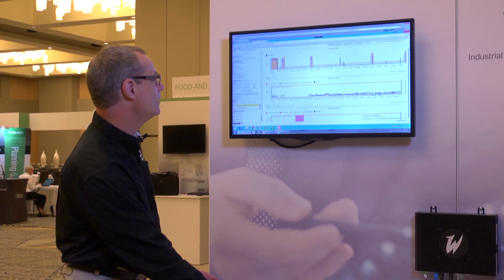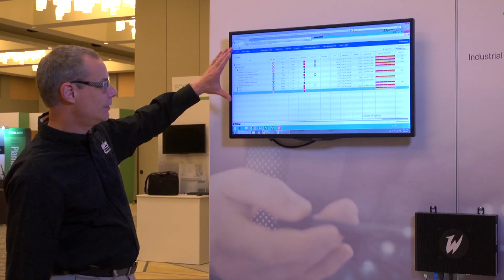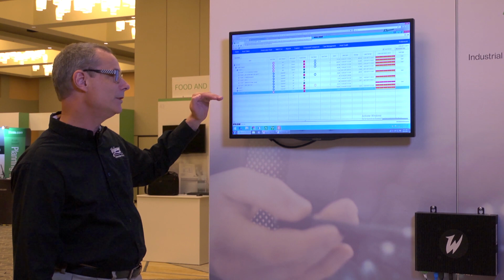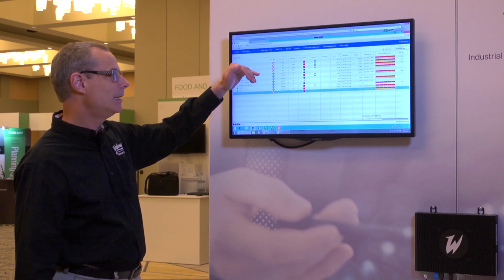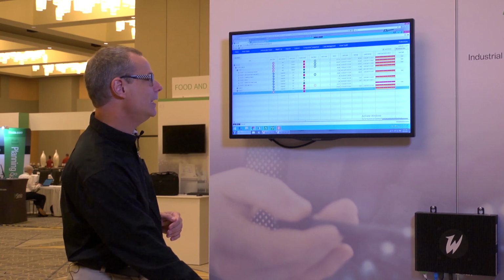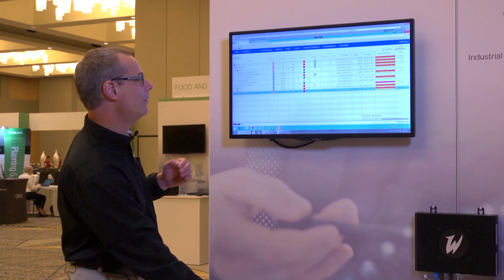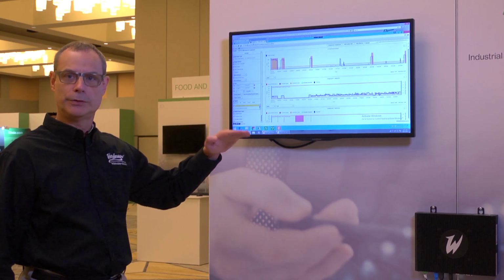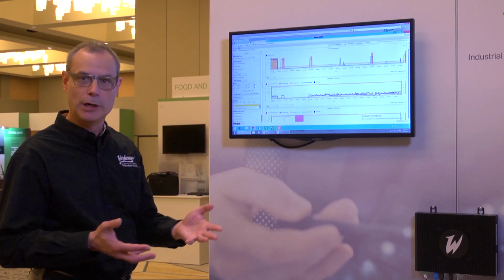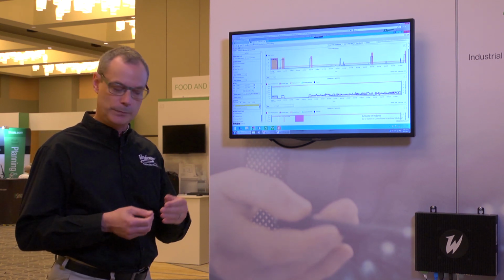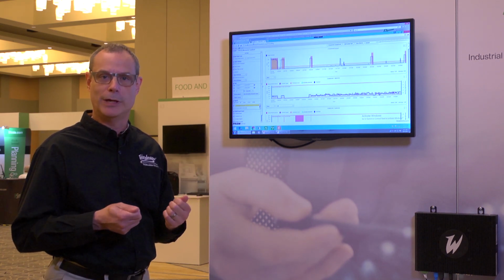the system has detected in this screen a series, it is monitoring a series of pieces of equipment, assets, and detecting an alarm state for one piece of equipment. And once we see that, we can go into the details of that piece of equipment and understand which of the variables involved in the model, the predictive model of Avantis Prism, has been causing the deviation from normal operation.